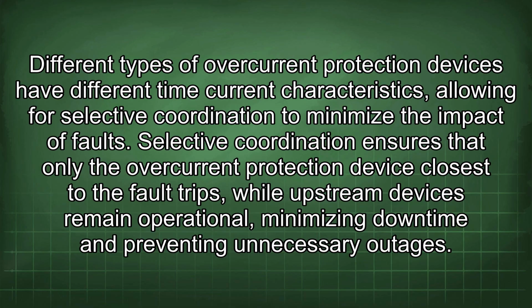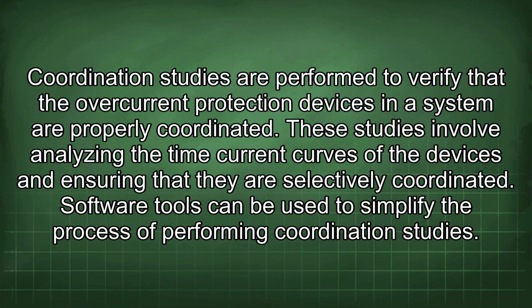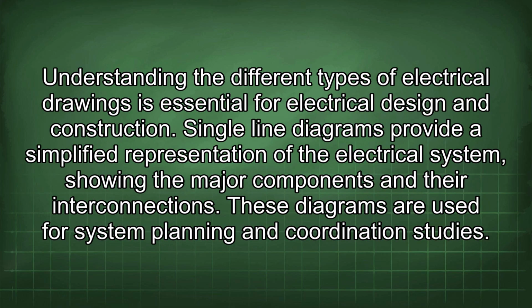the impact of faults. Selective coordination ensures that only the overcurrent protection device closest to the fault trips, while upstream devices remain operational, minimizing downtime and preventing unnecessary outages. Coordination studies are performed to verify that the overcurrent protection devices in a system are properly coordinated. These studies involve analyzing the time current curves of the devices and ensuring that they are selectively coordinated. Software tools can be used to simplify the process of performing coordination studies. Understanding the different types of electrical drawings is essential for electrical design and construction.